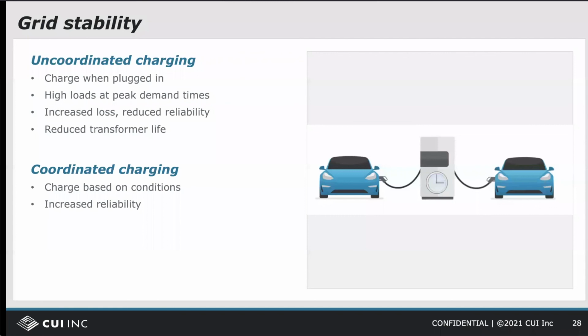As more and more EVs end up on the road, there will be more that are charging at any one time. As with everything, there will be peak demand times and low demand times. This can cause large imbalances that reduce the quality of the grid power, reducing the life of or even overloading transformers, and has led to the development of coordinated charging strategies.